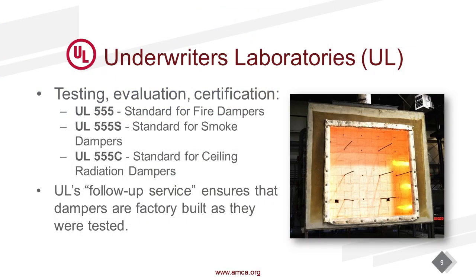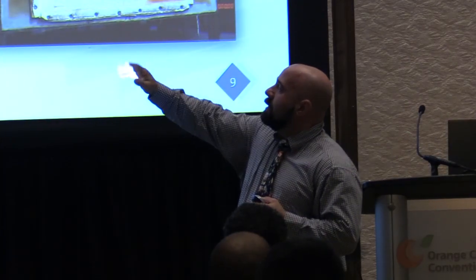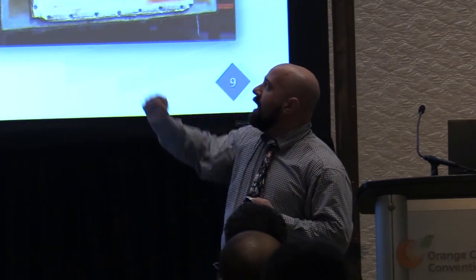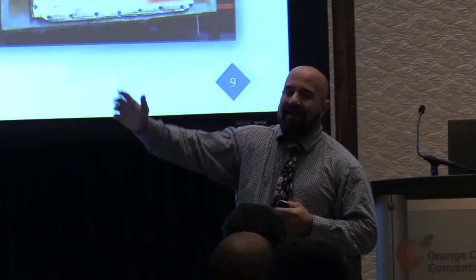When we talk about dampers, we always have to start with UL, Underwriters Laboratories. They are the preeminent certification and testing laboratory in North America. So we always reference their test standards. They're referenced by the International Building Code. So our life safety dampers go through what we call the 555 series of tests. UL 555 for fire dampers, 555S for smoke dampers, 555C for ceiling radiation dampers.